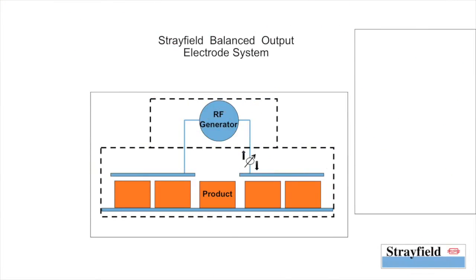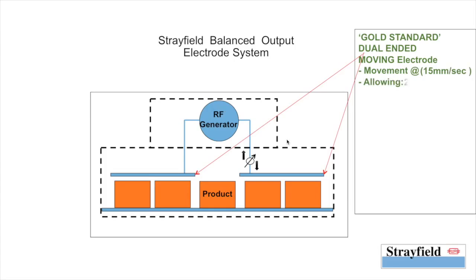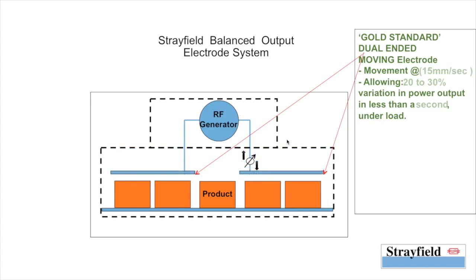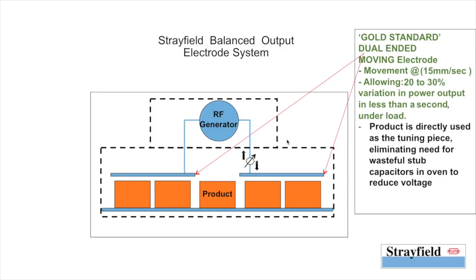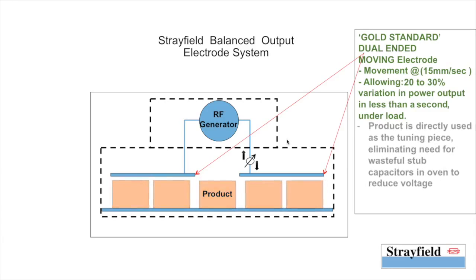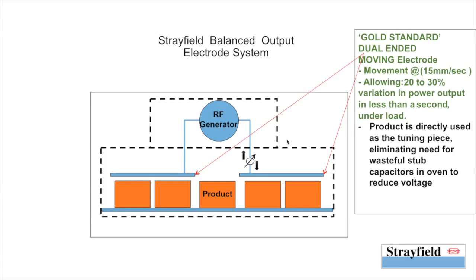Now let's compare this with the Strayfield balanced output electrode system. It is the gold standard with a dual-ended output and a moving upper electrode. It moves at about 15 mm per second and allows 20 to 30% variation in power output in less than a second when under load. Now the product is directly used as a tuning piece in this case, eliminating the need for any stub capacitors to reduce voltage in the oven.